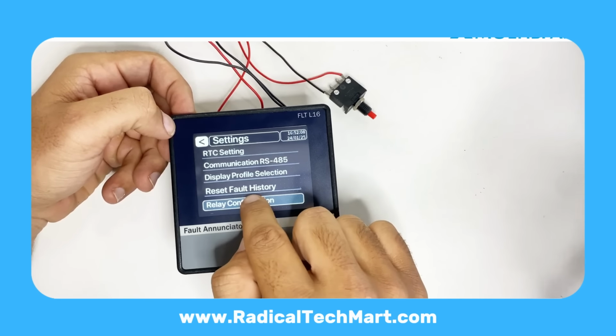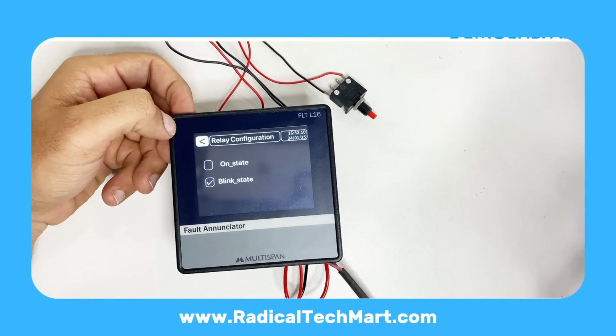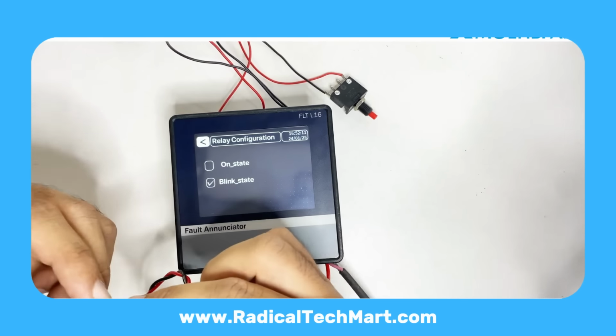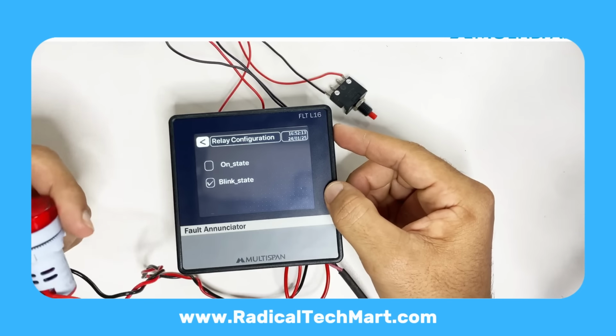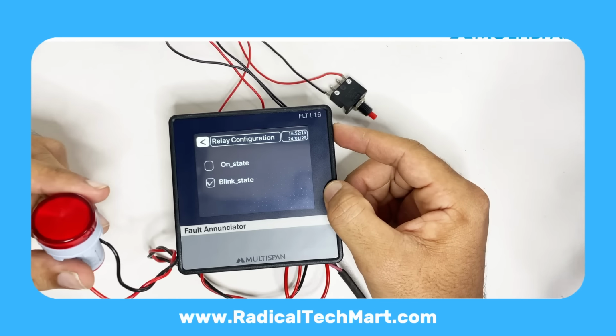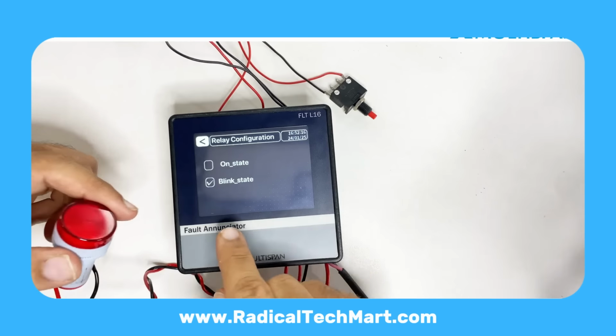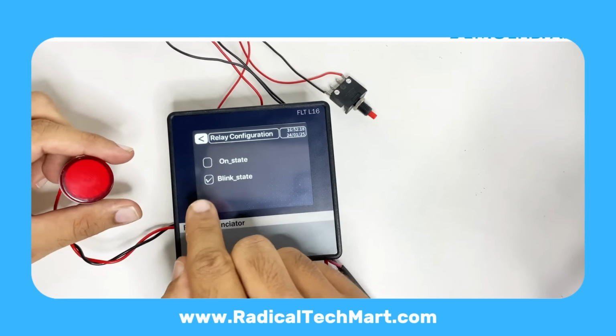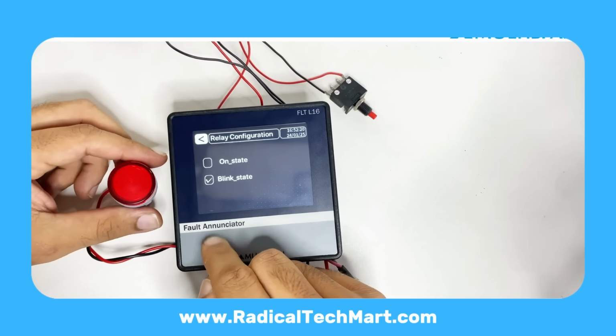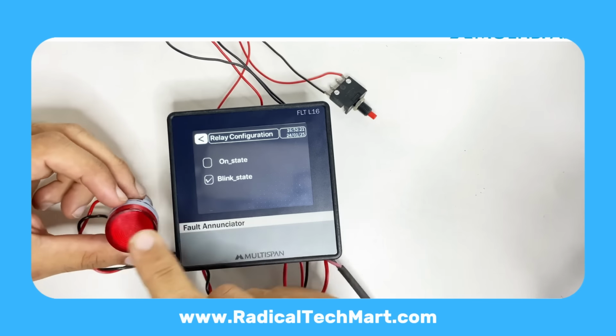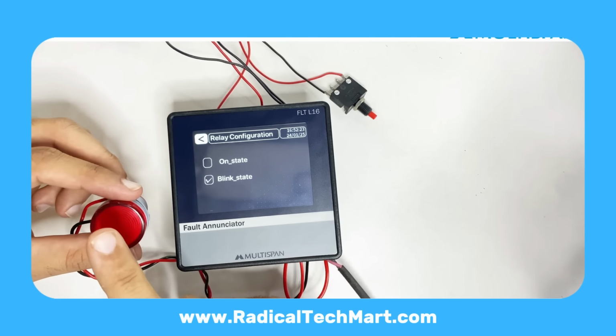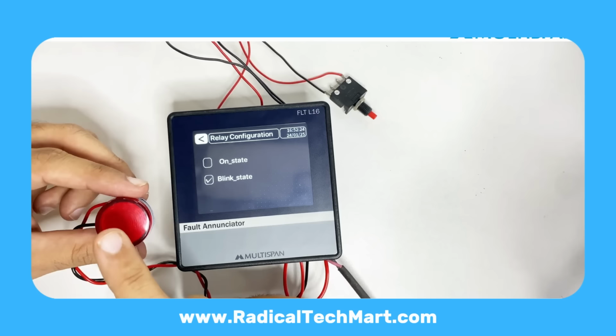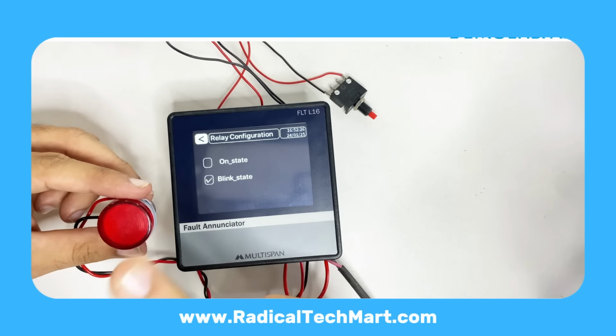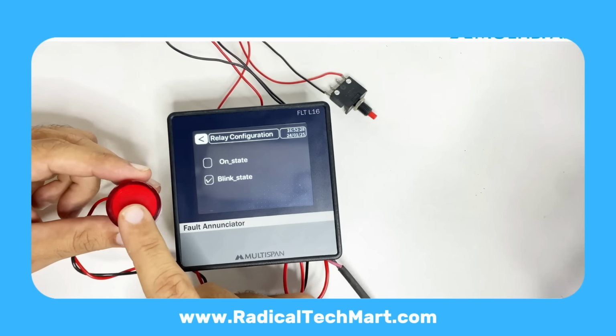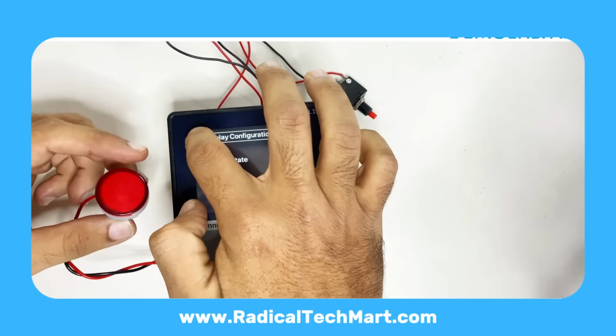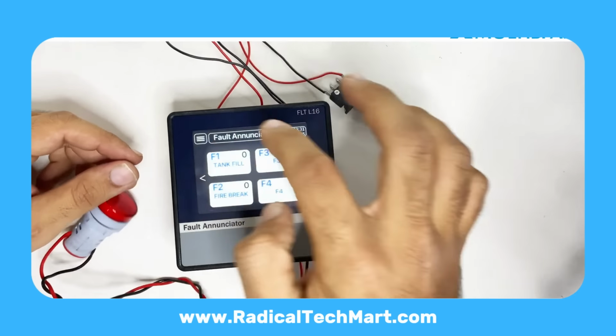Then we have Relay configuration. By default, Relay 1 is assigned for alarm. Relay 2 is assigned for trip. For Relay 1, you can choose blinking mode. The relay turns on and off repeatedly when a fault is active. Or constant on or off. In our demo, we have kept Relay 1 in blink mode. So whenever a fault comes, the alarm relay will keep turning on and off, and the LED connected to it will also blink, attracting attention. Relay 2 can be used as a trip relay, wired to shut down critical equipment when certain fault conditions occur.